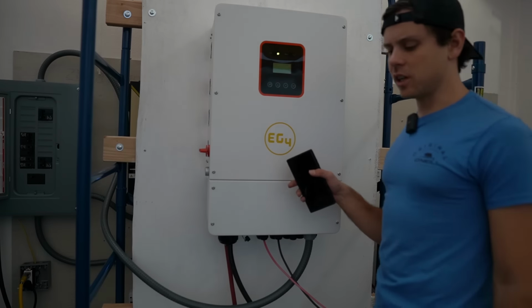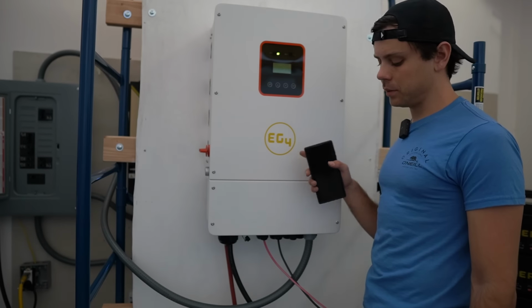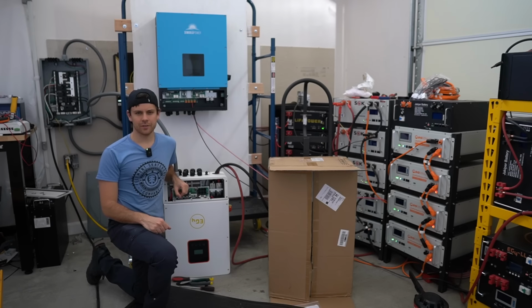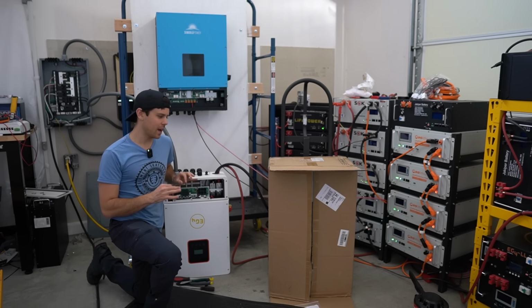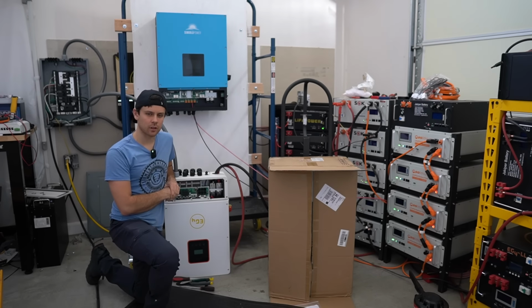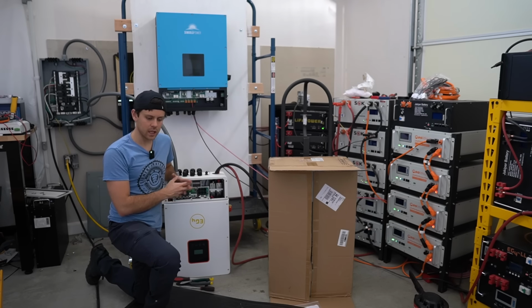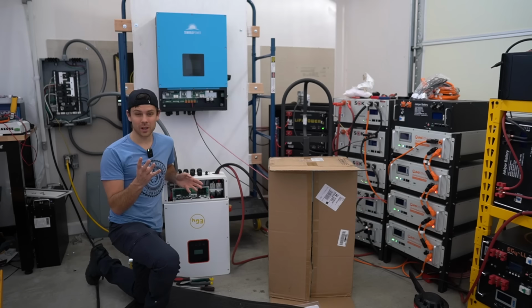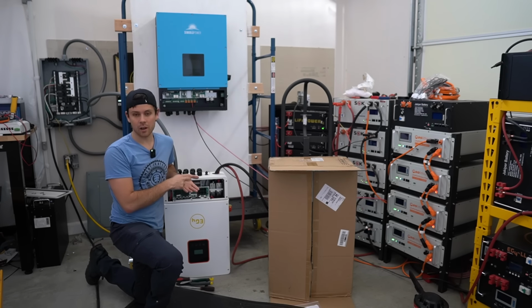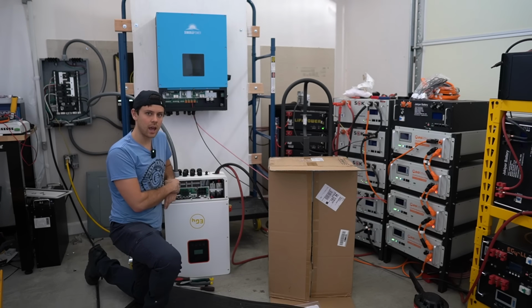Uh-oh, I think I need to change the settings because it keeps shutting down, so I'll be back in a day. So fast forward a few days later, and I'm unfortunately having an issue with this 8K inverter. Every time I connect it to an EV charger, it trips its internal GFCI. And I've tried 4 different EV chargers, and I've tried all of those chargers on the grid and with other inverters without any issues. But when it's connected to this 8K inverter, it trips the internal GFCI.